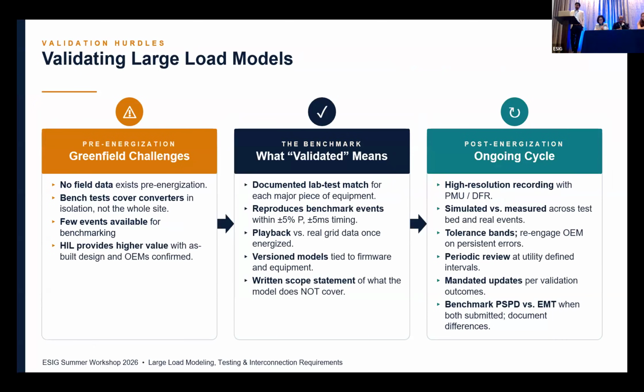Now, challenges, as I mentioned earlier: for greenfield sites, you don't have any field data. It's pre-energization, while there might be some factory tests for converters specifically, but for the complete site itself you don't have a validated model. So while you can do benchmarking against PSSE, EMT, and RMS models, benchmarking against on-site data isn't possible early on. Hardware in the loop provides some good value, but probably provides more value once you have actual as-built designs and OEMs confirmed.